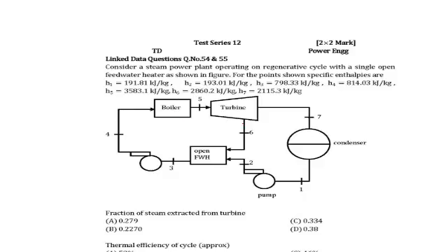So here, let's just imagine that a unit kg is flowing, for simple purposes. Let's say y is the fraction of steam removed, so y kg is removed, and the remaining 1 minus y will be flowing through this, and ultimately they will again combine in the open feed water heater, where there is no additional heat supplied. It is just the water that is used to heat.